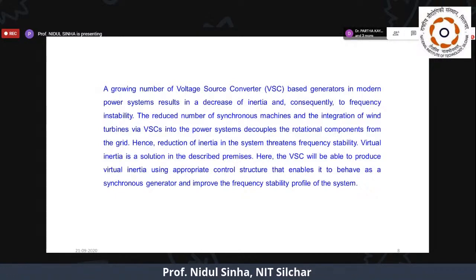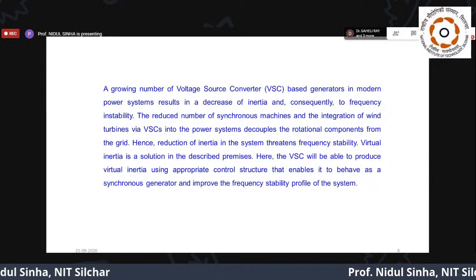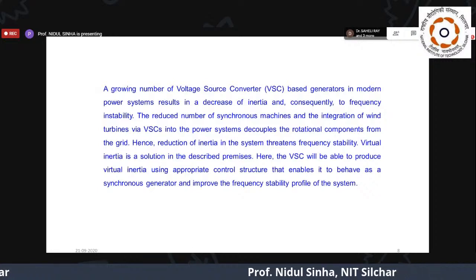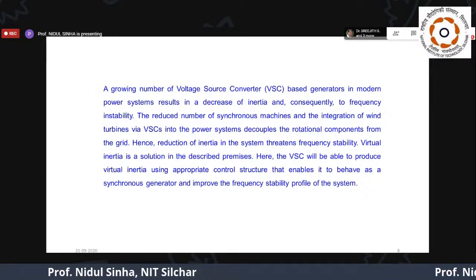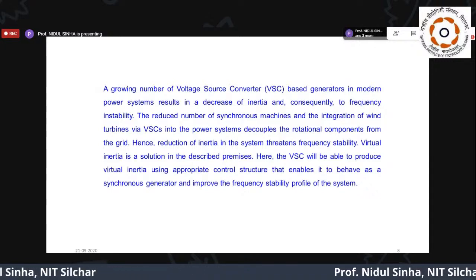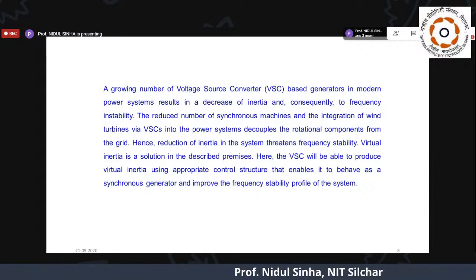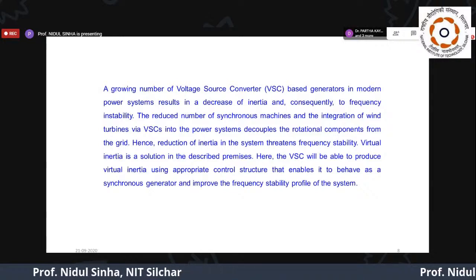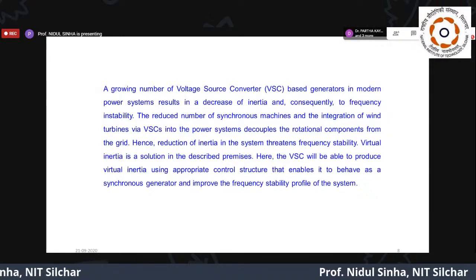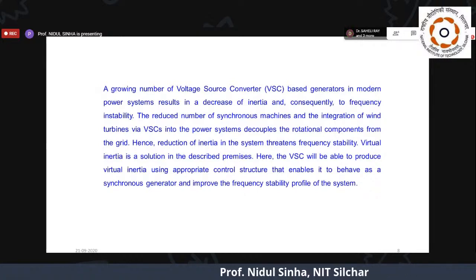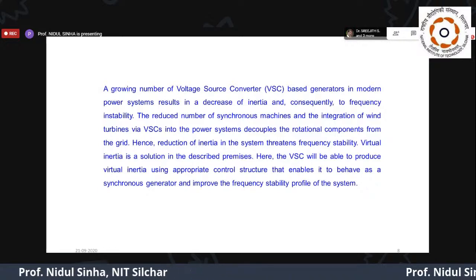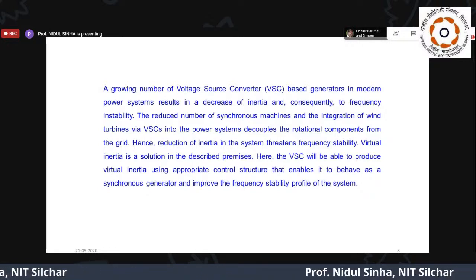When you go for the power converter, in future this will be the reality, as I said. Then in that case it will result in reduced inertia, and frequency instability will be there. Because there is a much faster response, minor disturbances in the real power imbalance will result in variations in frequency, and some relays are made to respond to these frequency variations.